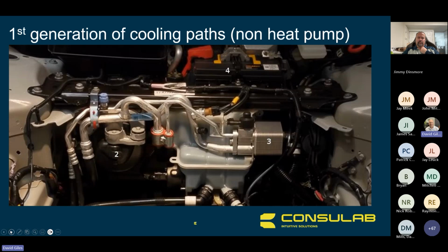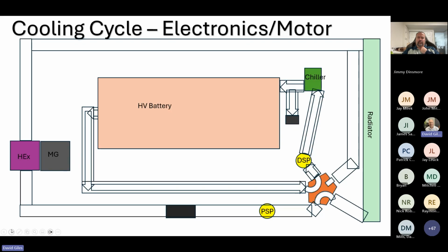So, first generation of cooling paths, non-heat pump. I have a kind of a shady little PowerPoint here to explain it, just to give an example. This is the electronics. In the very bottom right corner, that little orange hex box represents not the Octovalve, but the four-way valve. In fact, it's actually 5 valves on it, but 4 are only for passages, and 1 is a blocker.